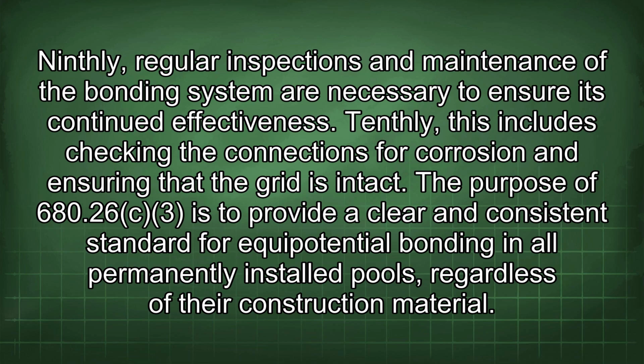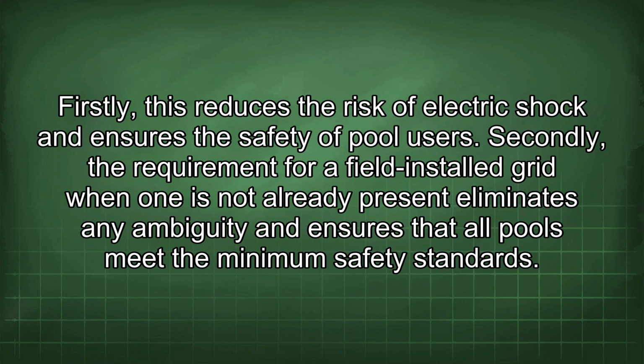The purpose of 680.26(c)(3) is to provide a clear and consistent standard for equipotential bonding in all permanently installed pools, regardless of their construction material. Firstly, this reduces the risk of electric shock and ensures the safety of pool users. Secondly, the requirement for a field-installed grid when one is not already present eliminates any ambiguity and ensures that all pools meet the minimum safety standards.